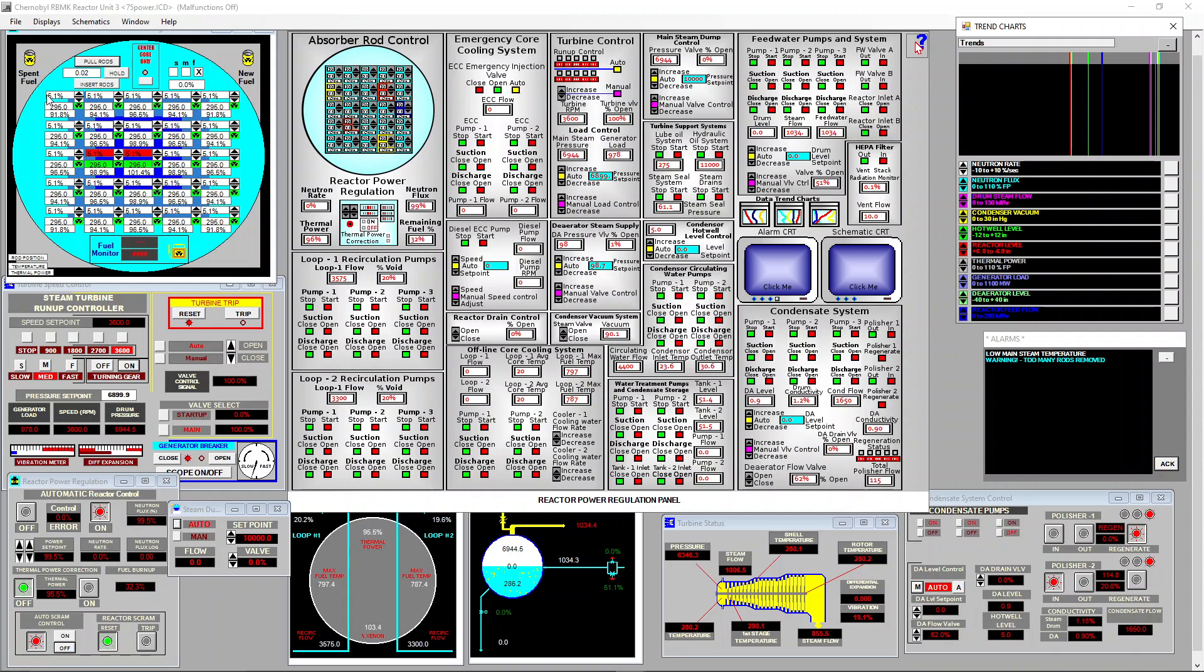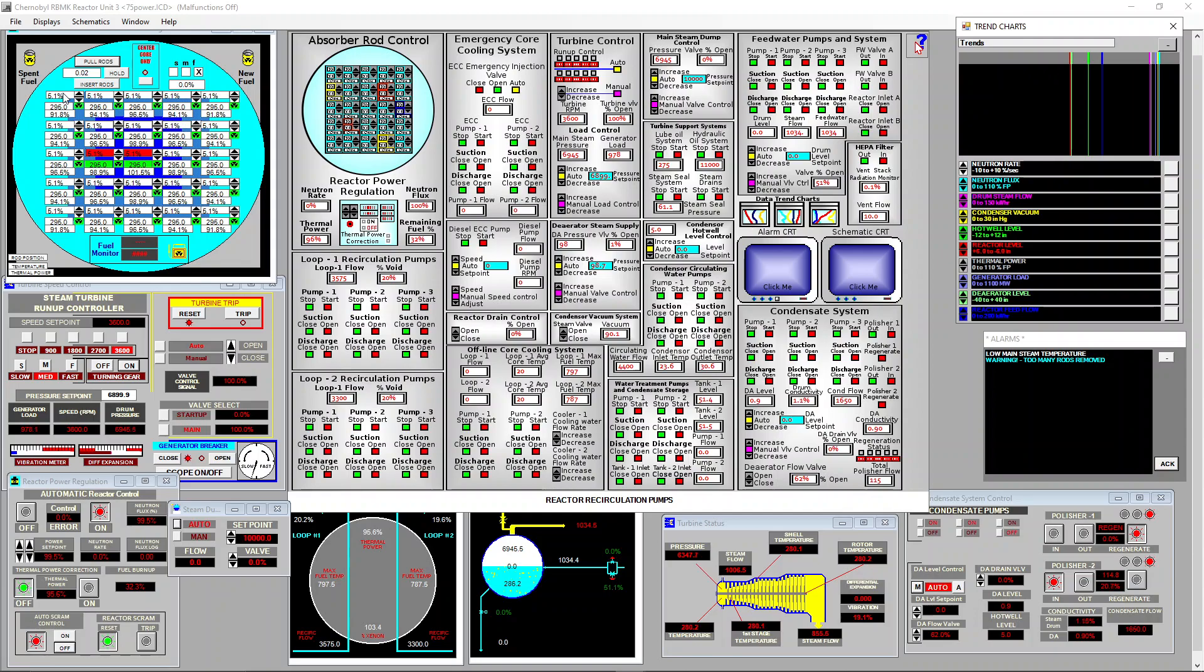But we are really at the edge. I think the edge is around 4.9 percent. It depends on xenon concentration, boiling and other things, but I think in the configuration we are now just a 0.2 to 0.3 percent withdrawal of rods will mean loss of controllability. It means a drop of neutron rate to zero really fast, like in few seconds, and then the reactor is stalled because there is no way to bring the reactivity back.